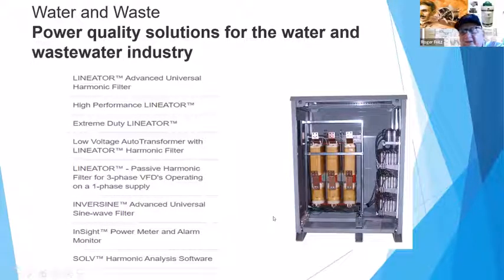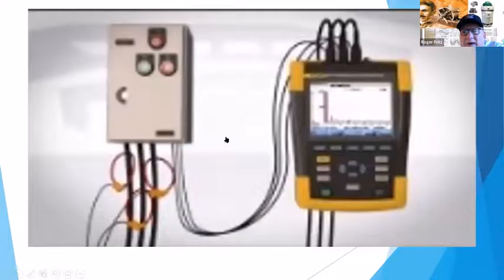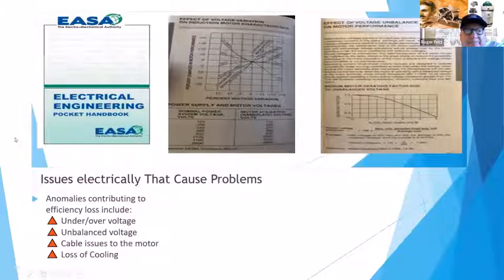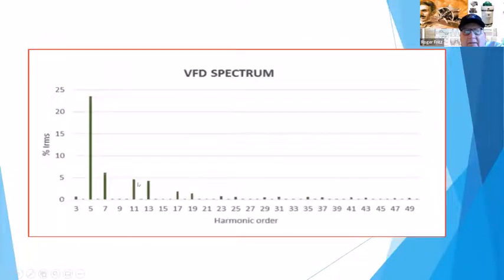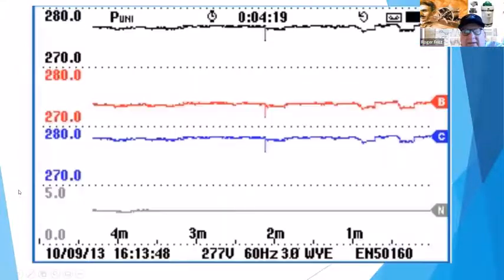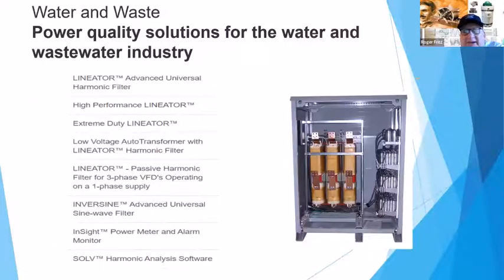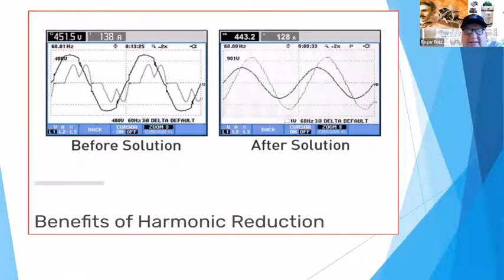There are various types and brands out there, but what they are is another set of coils, which are inside the circuit. They go in series with the load, and then they have a group of capacitors in here that are tuned to basically wipe out and clean off these harmonic orders, either on the input or the output. And so the factors that I've also found, in application and design, is that it's very important.